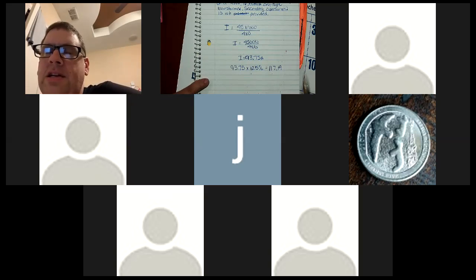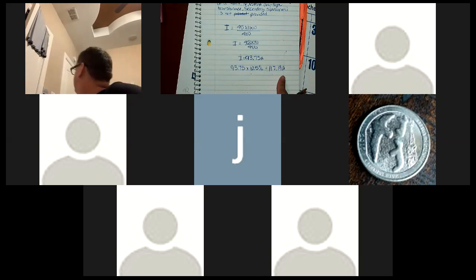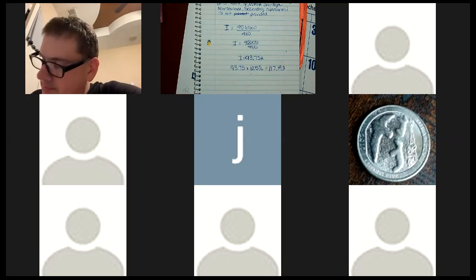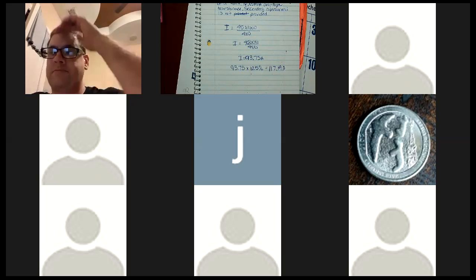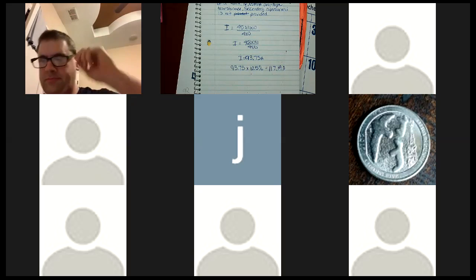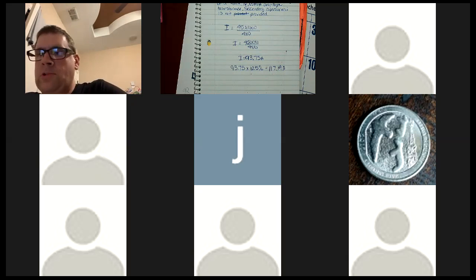Yeah, so okay, we're all in this together right here. We're at 117 amps, and now we're going to go over to our sizing, our standard fuse rating sizes. So we're going to go to 240.6, right? 240.6A. If I have 117, what am I going to do, am I going to go to 110 or 125?